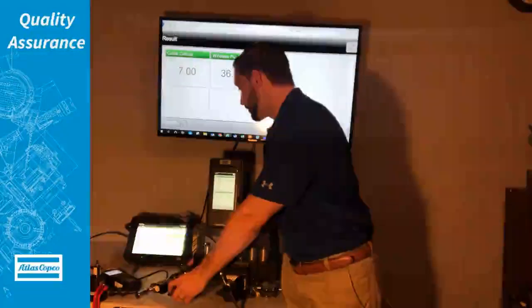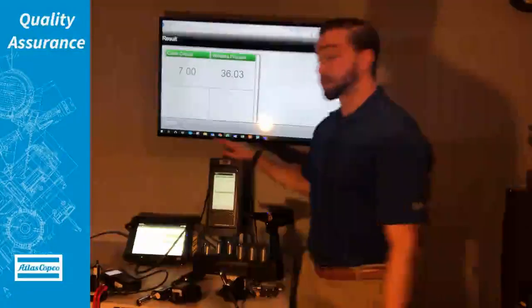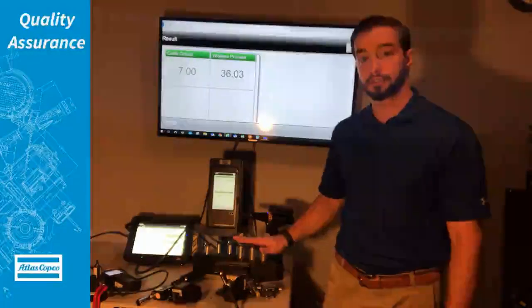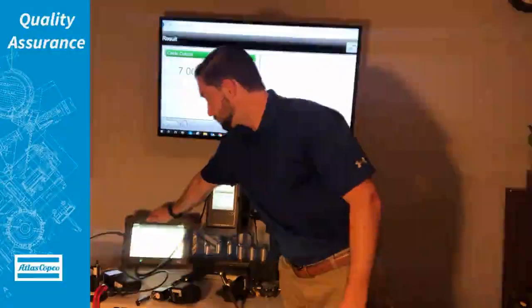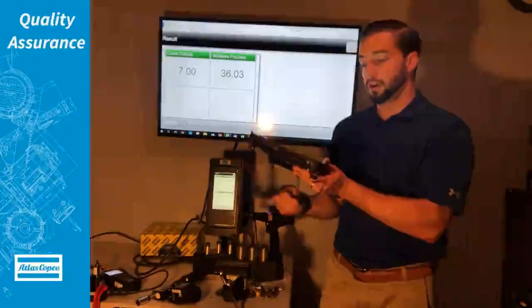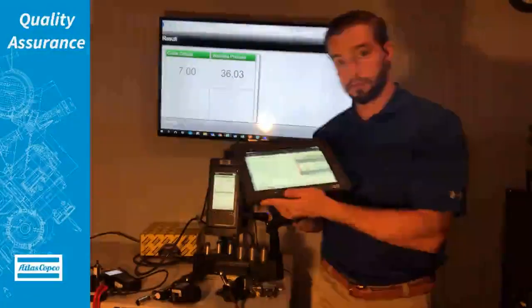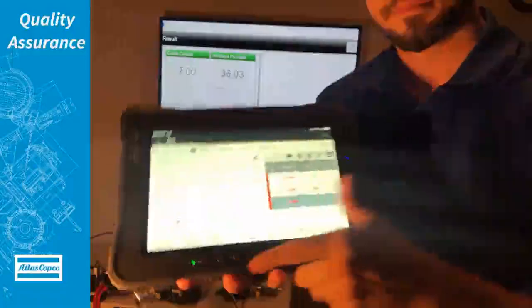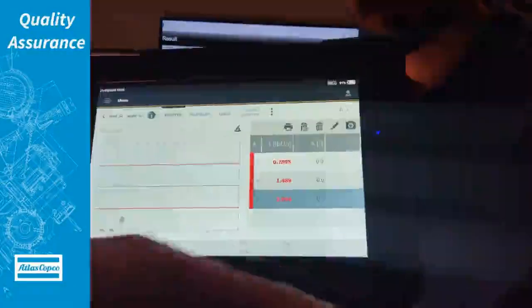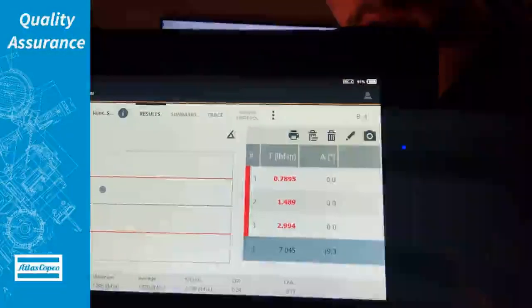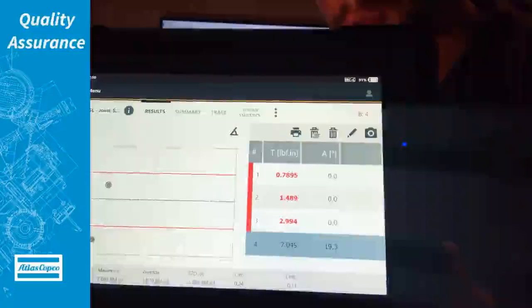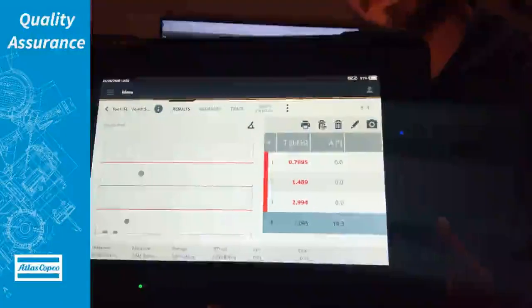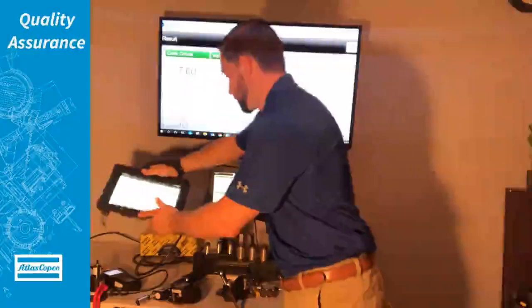You can see we got seven inch pounds on our controller screen from the internal transducer of the tool and it will come to our ST pad. Results are still loading in and we got our latest there, 7.04 from our external transducer.